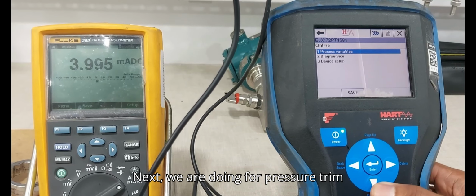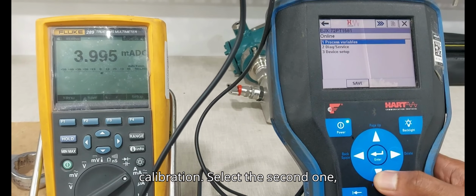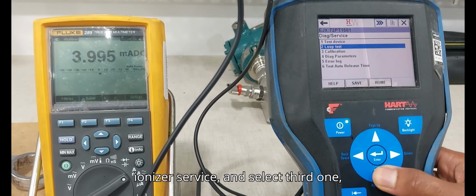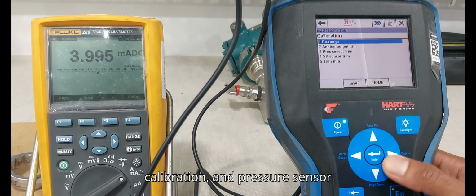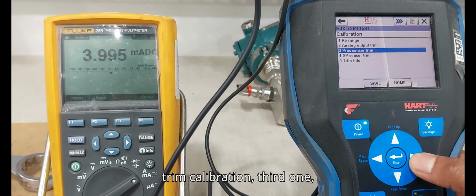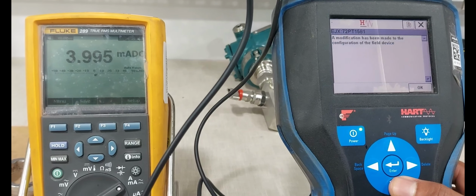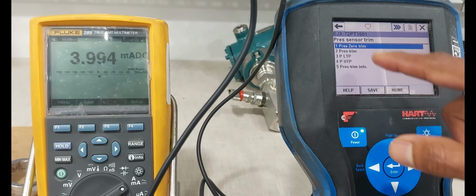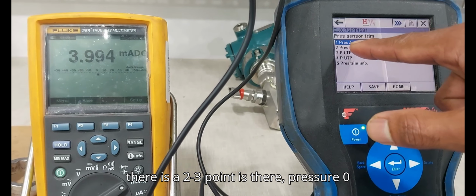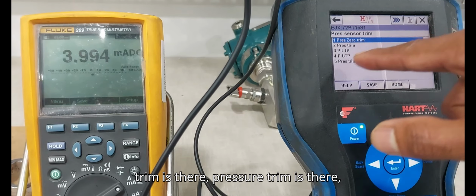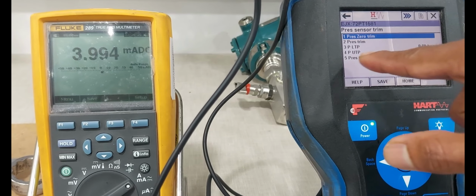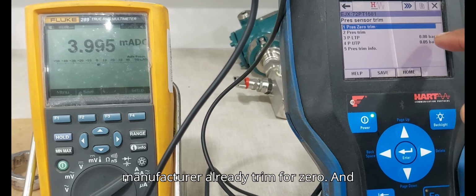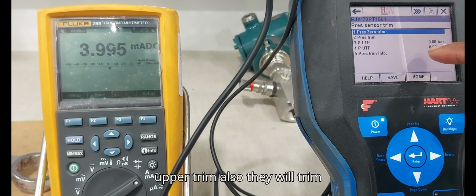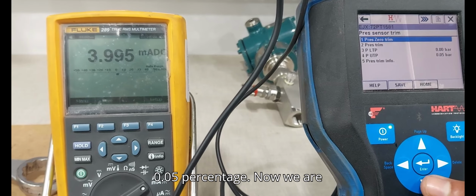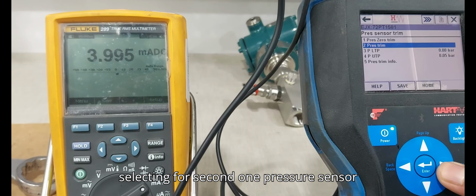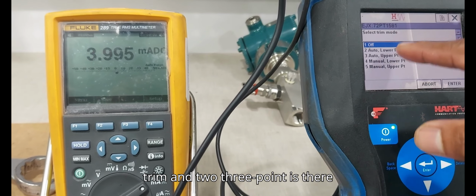Next we are doing pressure trim calibration. Select the second one, diagnostic service, then the third one, calibration, and pressure sensor trim calibration. There are 2-3 points. Pressure 0 trim is there. Pressure trim is there. Manufacturer trim point is also there. The manufacturer already trimmed for 0, and the upper trim also, within 0.05 percent. Now we are selecting the second one, pressure sensor trim, and 2-3 point is there.